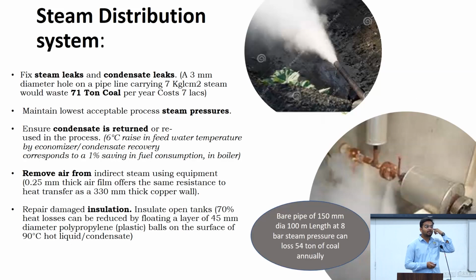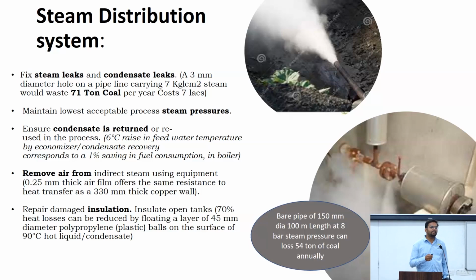Then a significant energy reduction we found everywhere is from steam leakages. Now, why do steam leakages happen? We generate steam at a specific saturation condition, but during travel, because of insulation losses, the steam converts into some moisture, and dryness fraction is introduced. Wherever there is a joint there is a gasket fitting, always, because the steam line is a big distribution. So that is the weakest part, and whenever there is excess moisture in the system, it will create leakages.